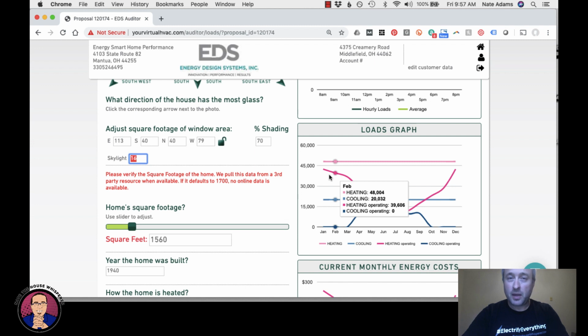The heating load is Manual J, which has 3 fudge factors. It has a fudge factor assuming the equipment won't perform to spec. It has a fudge factor assuming that the ductwork won't perform to spec. And it has a fudge factor on top of that just in case. Now that's for heating. For cooling, it's a lot closer. But for heating, we found that we can discount Manual J 30 to 60% when we get into tighter homes and still handle worst case.